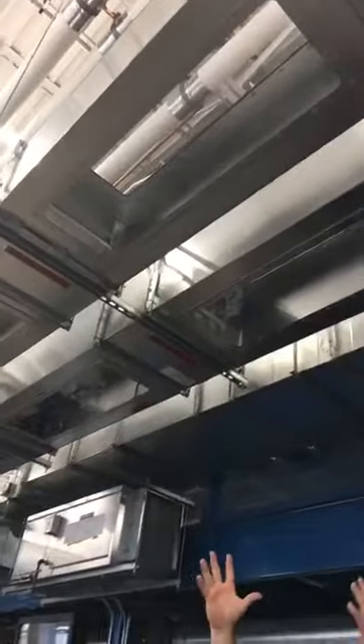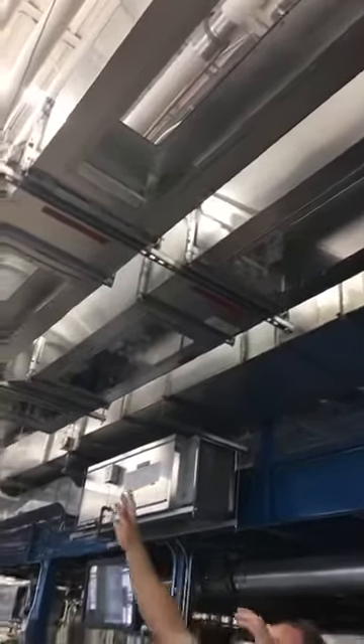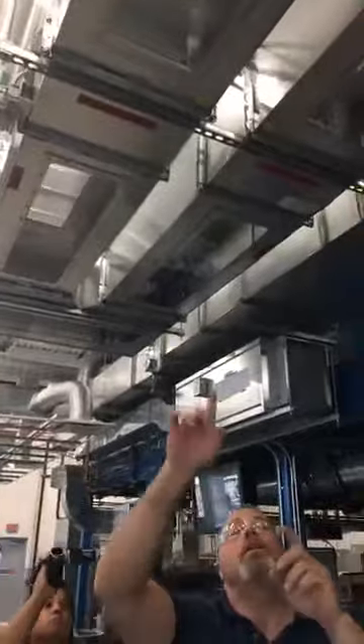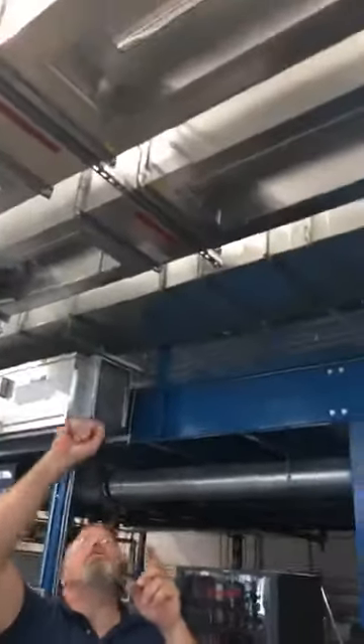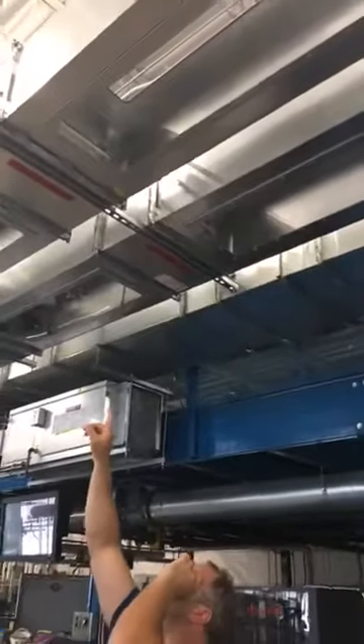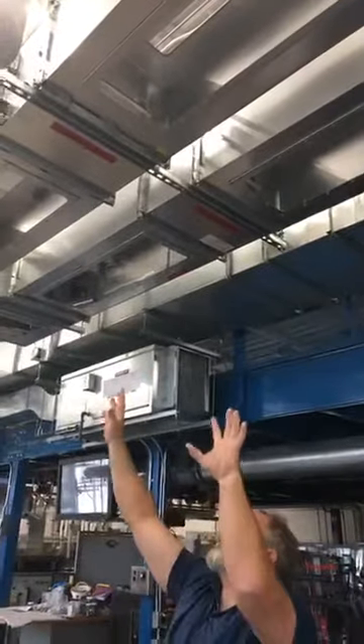And then we have an isolation damper, which is on one fan. The other one we do not have an isolation damper. That's so we can capture the smoke in a compartment and then clear another compartment. I guess we don't really have a very good fire smoke damper one. This would be the area that we'd be able to capture our smoke and then clear smoke.